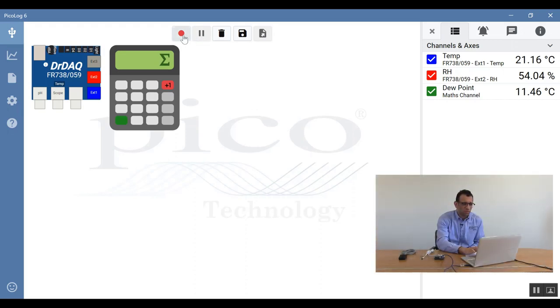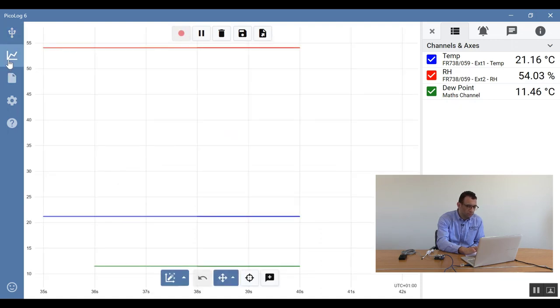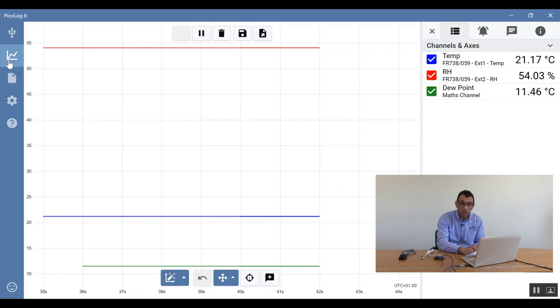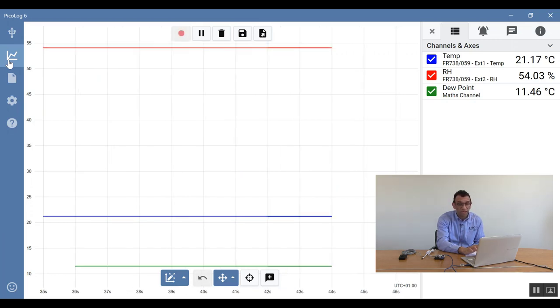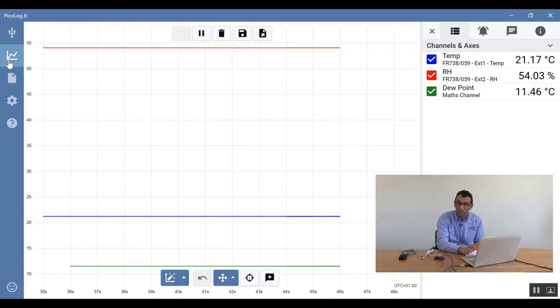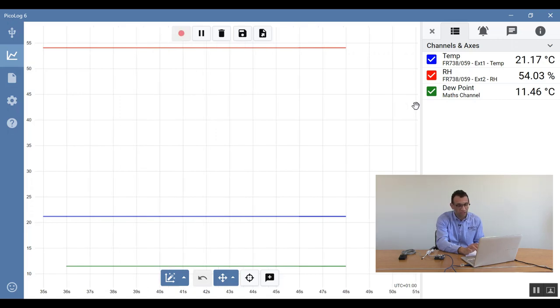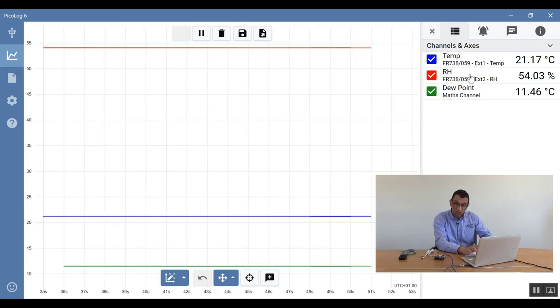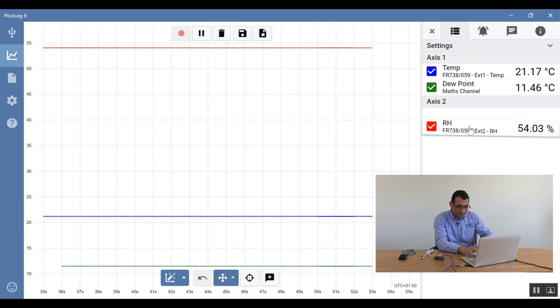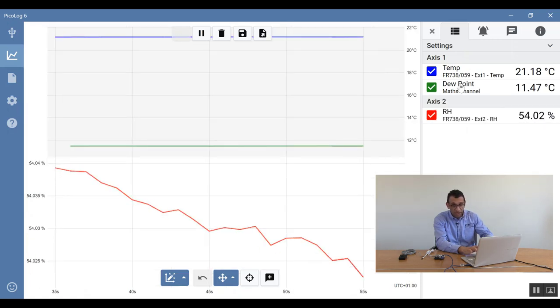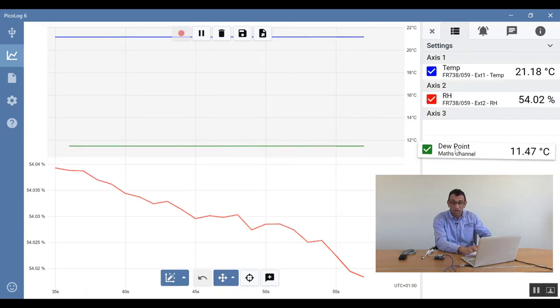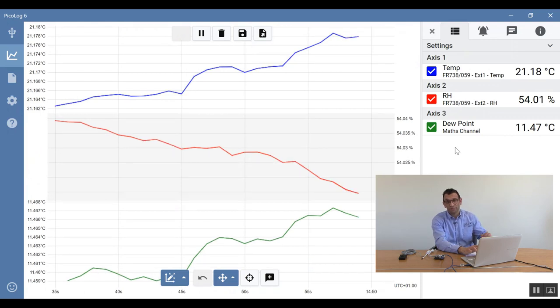I'll start by capturing some data and go to the chart view. You can now see three separate readings on one graph. Two of them are temperature and one of them is a percentage. We can drag the RH one, which is in the percentage form, down, and you can see it goes to a second axis. You can actually have up to four axes.